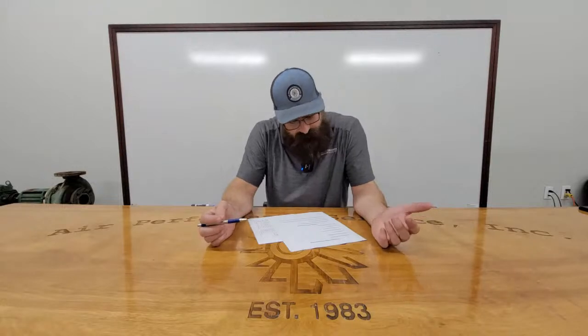So next, we can talk about a chill water air handler with VAVs. Same basic thing. Chill water control is just like a single zone, except you're maintaining discharge temperature 9 times out of 10. I don't know many people that maintain return with a chill water air handler, but it is possible. You could do it. We just don't do it in Texas.